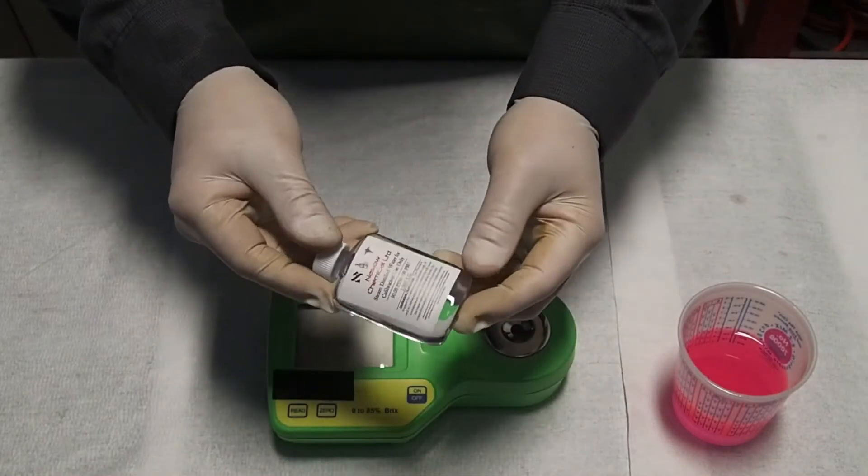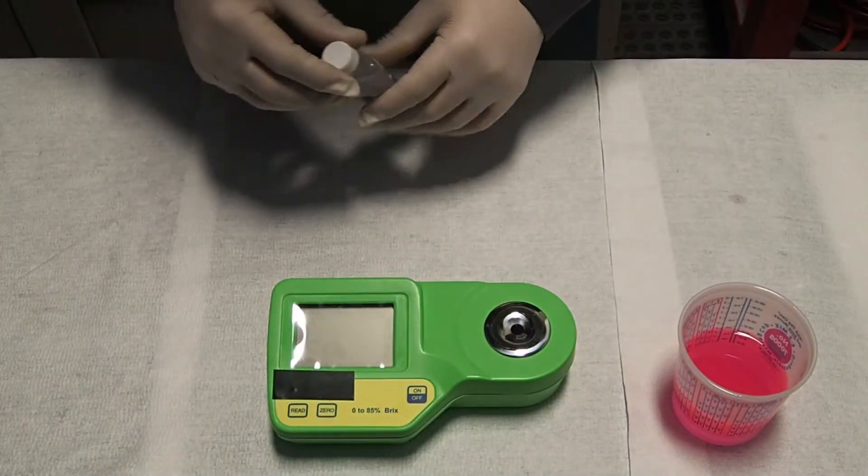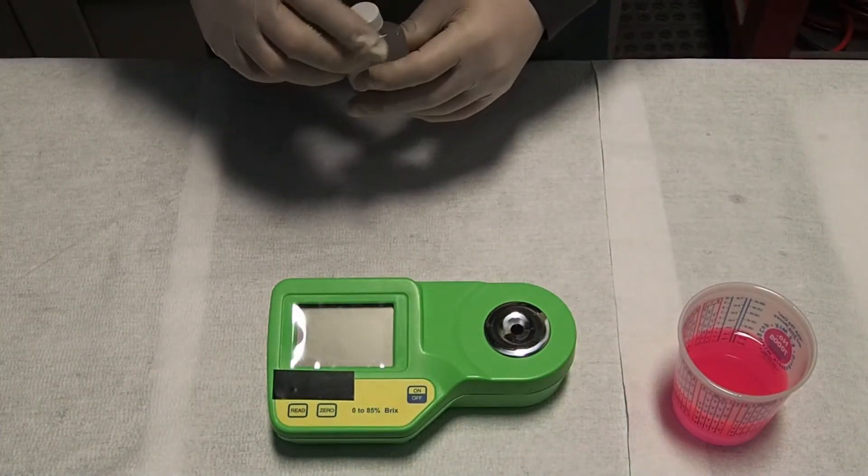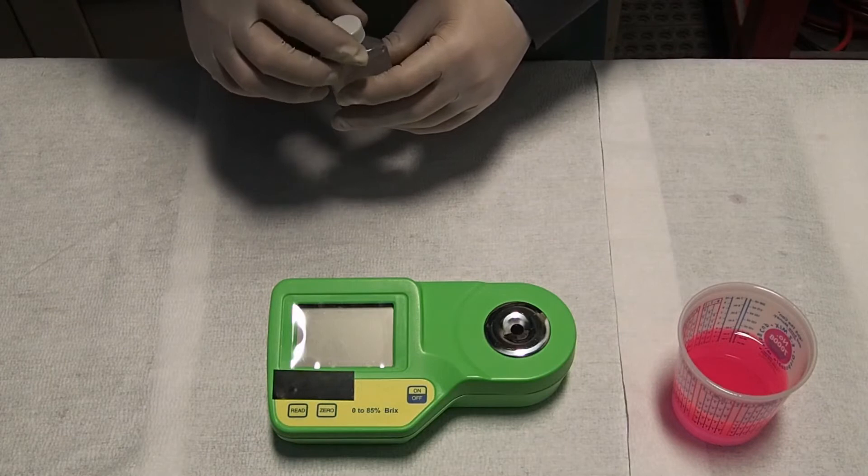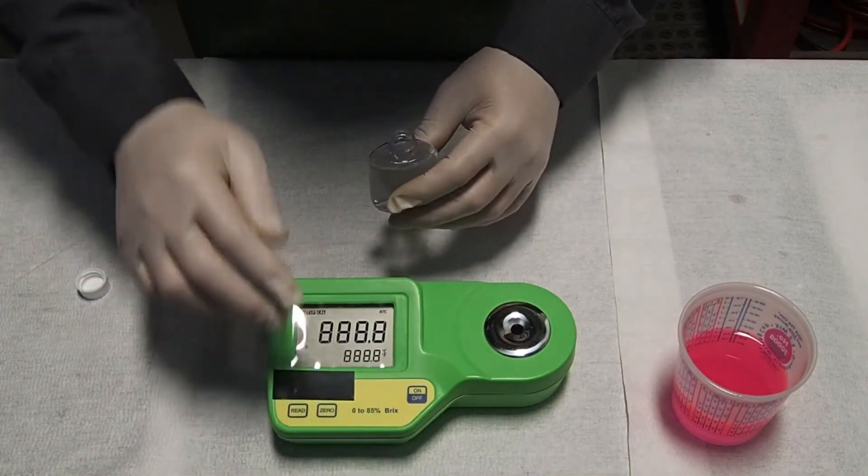To set up the zero point. This point is very important because it is the reference point used for the refractometer. Also, you can use deionized water to do this step. To run the device, the device will show us the power and the temperature because this device has automatic temperature compensation, or ATC.